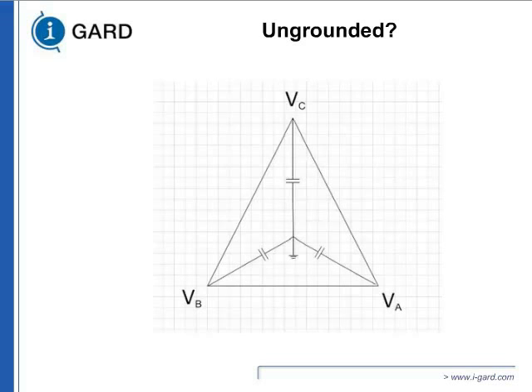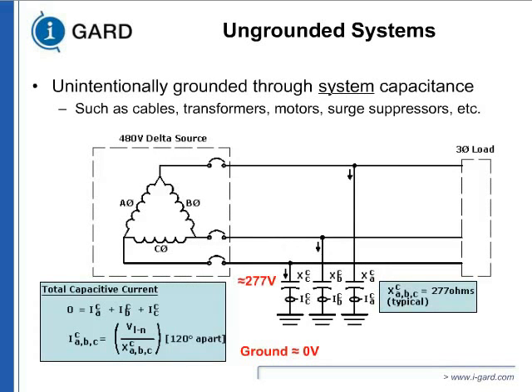So what happens in an ungrounded system? If there is no return path, the first ground, cable or transformer, couples basically to your system. You can see the three-phase system shown in front of you, and you have three capacitive couplings to the ground. You have cable insulation, you have air as a dielectric, and you have ground at a different potential. So basically, in a good system, when there's no ground fault, there's no voltage at all to the ground. Now let's see what happens when there is a ground on it. Okay?